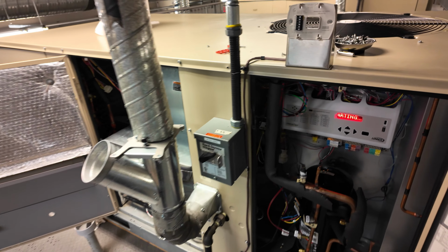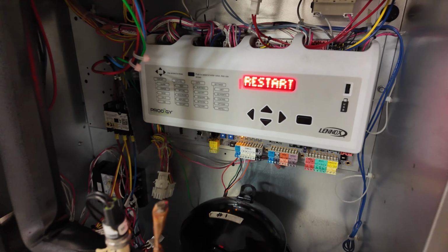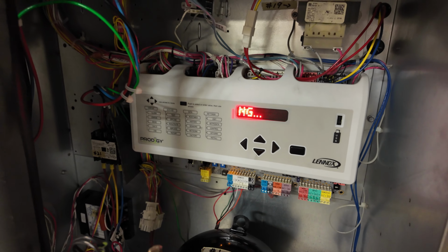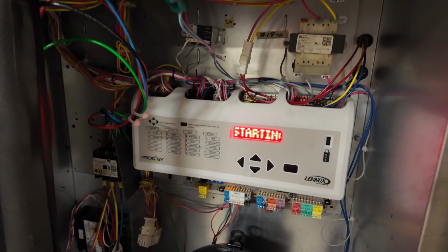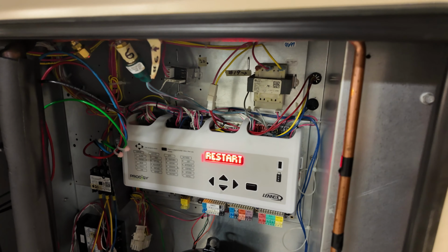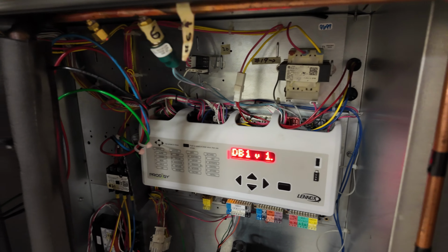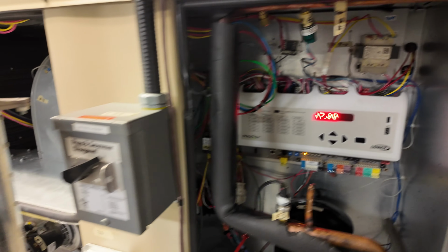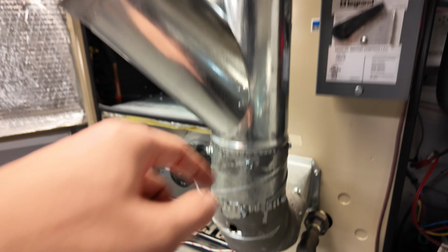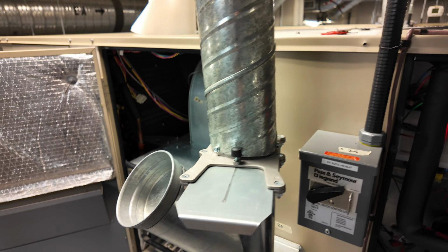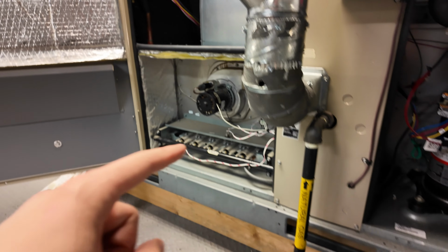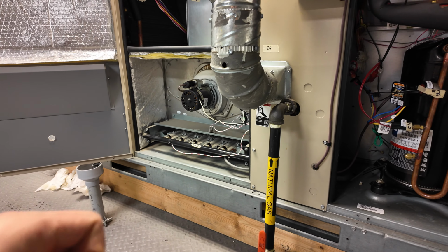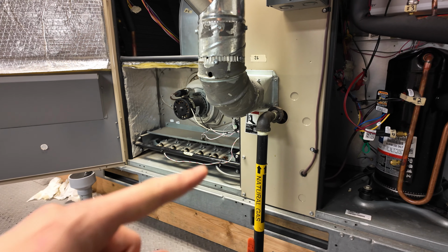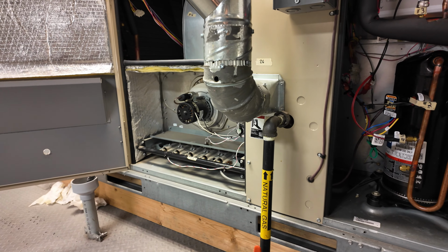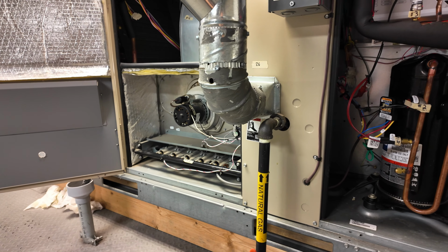fire it back up. You'll see on the Prodigy it's restarting, and then it'll switch to heating mode here in a second. It's in heating mode. Just heard the combustion motor turn on. Gotta make sure I now open my vent. That's when that pressure switch will close, and then it's going to send 24 volts through all the heating safety chain. Make sure all those safeties are good.